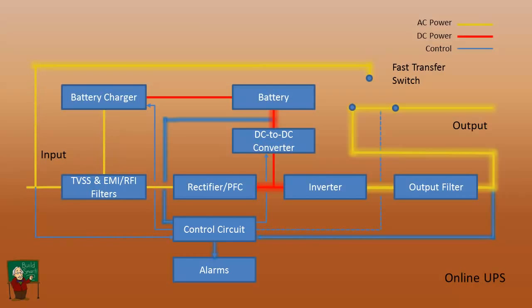If we lose power, you see that there's not a whole lot of change, nothing really transfers. We have an alarm for the lost power, but basically the battery is providing the DC that goes to the inverter instead of the rectifier. So no transfer, there's no break whatsoever in the output voltage.